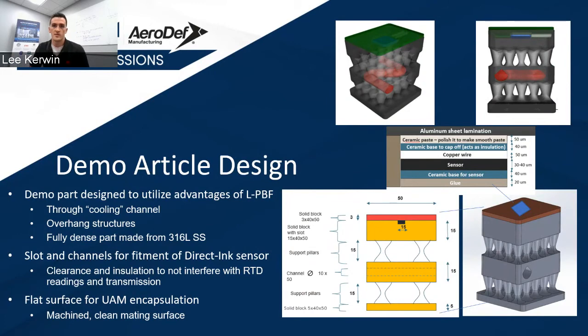You can see in the center on the right how we layered the sensor and what we put on top and bottom of it. We were concerned about the difference between coefficients of thermal expansion for all the different materials that we would put in there. We didn't want the sensor to crack or anything to break inside of there. So we put some ceramic paste, glue and epoxy in there to help with any deformation.